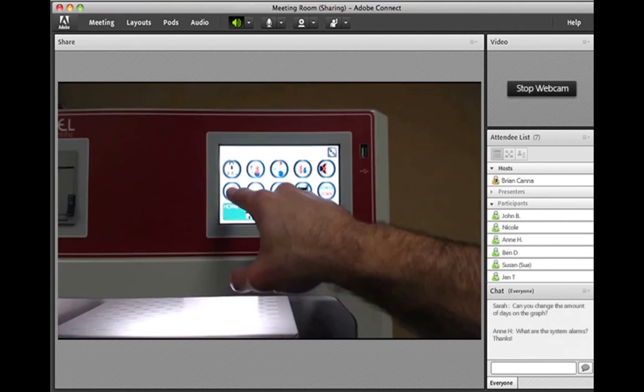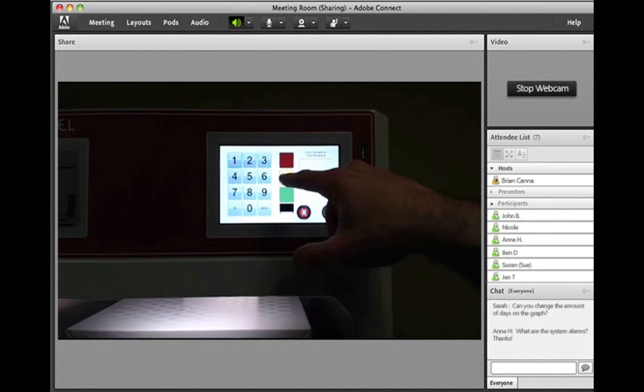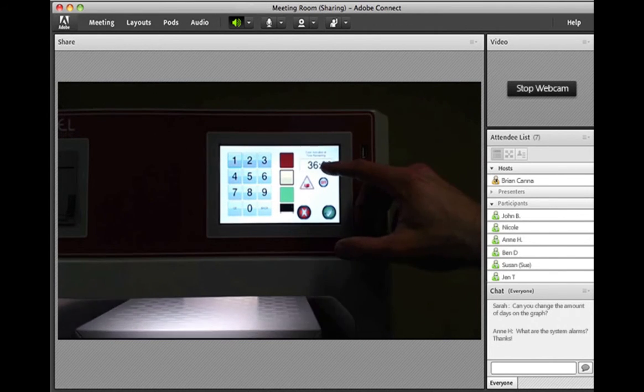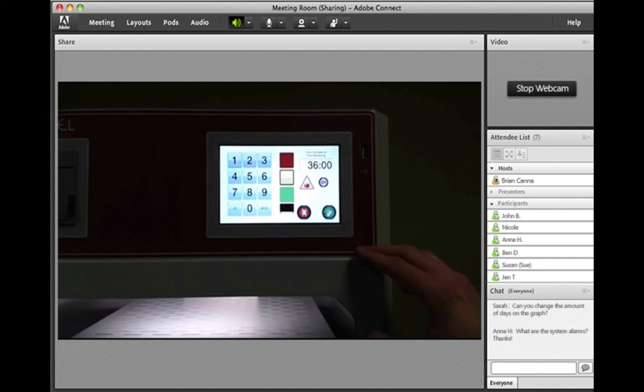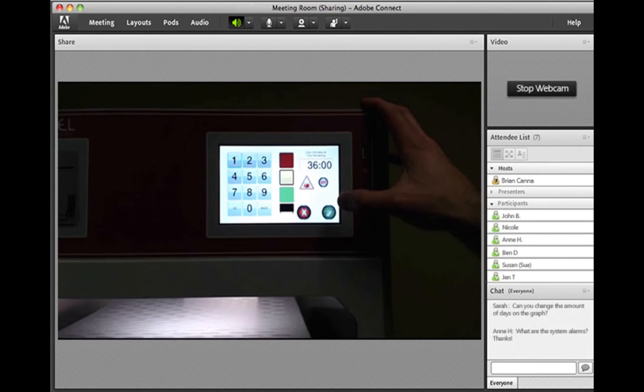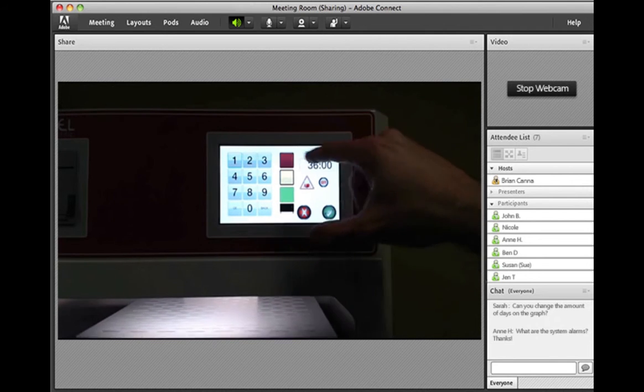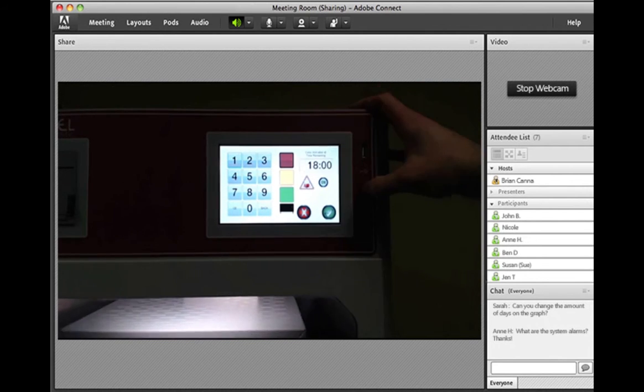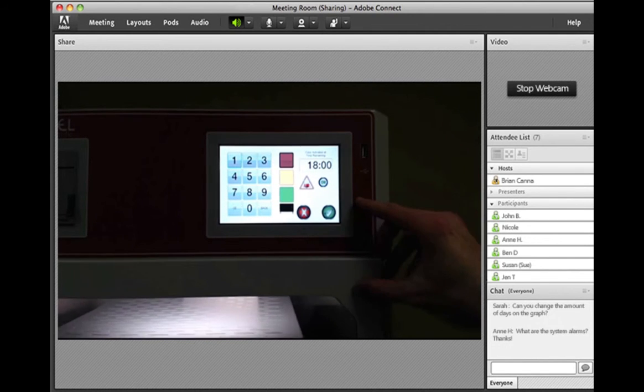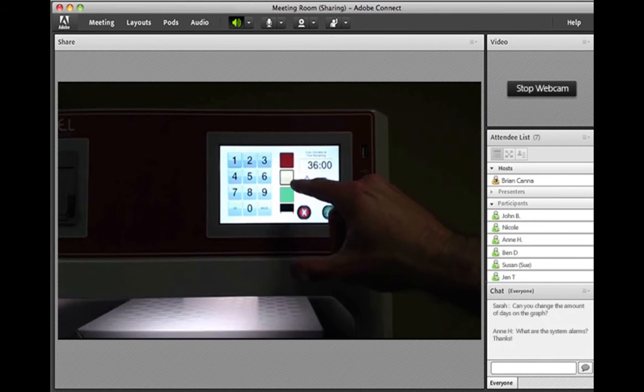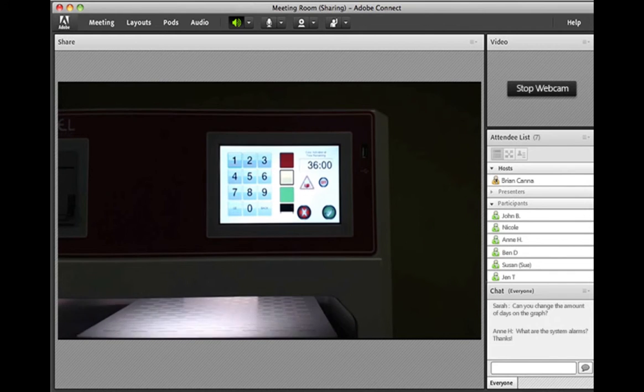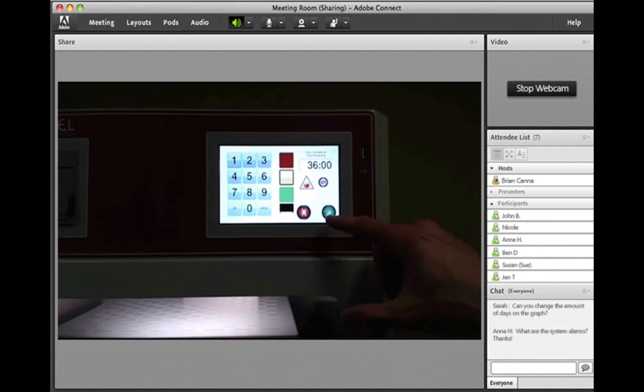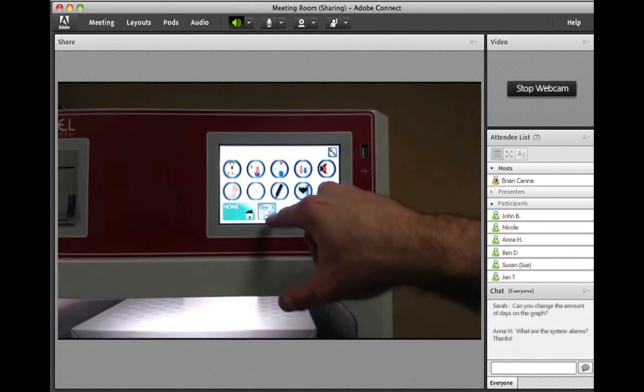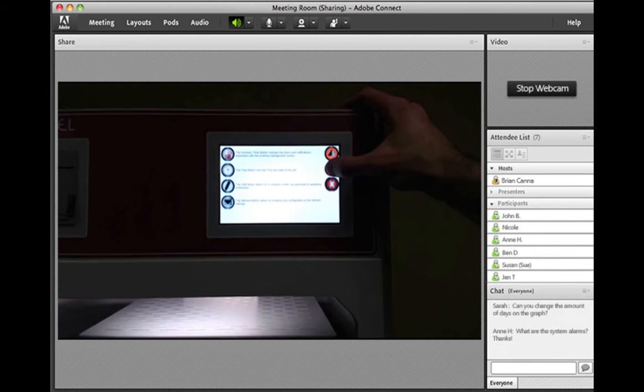Inventory management system right there, and what we'll do is we'll touch the yellow indicator. When inventory has less than 36 hours left, the shelf will turn yellow on the inventory management screen and on the screensaver. If it has less than 18 hours, the shelf will turn red and you will get an alarm. If you don't want this alarm, you can actually just turn it off. And as you can see, there's no alarm associated with the shelf turning yellow. So it's just a good way to keep track of your inventory so you don't have any bags expiring. So we'll go back to the help and run through some more of the alarms.